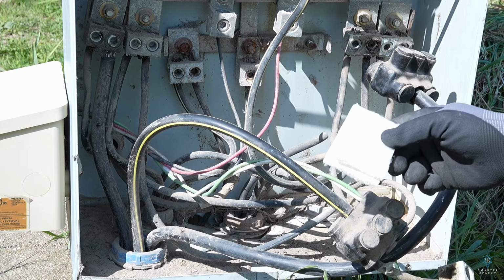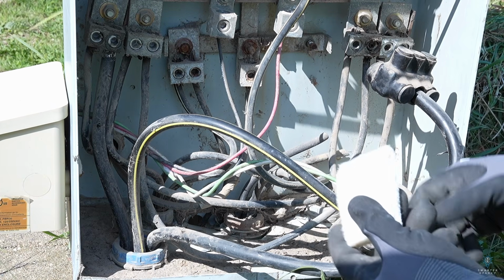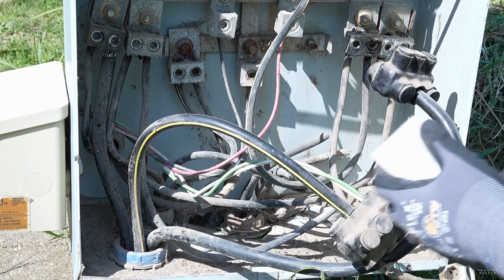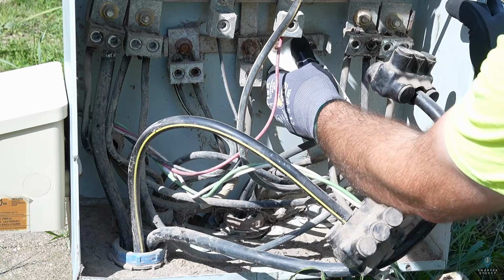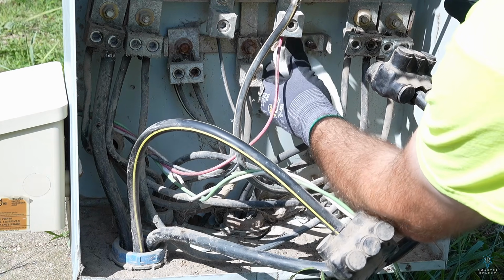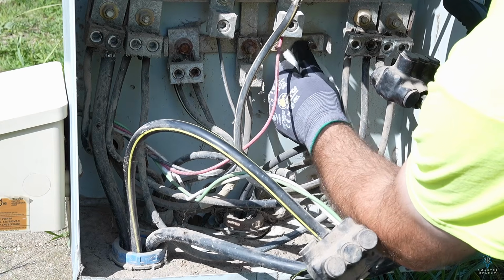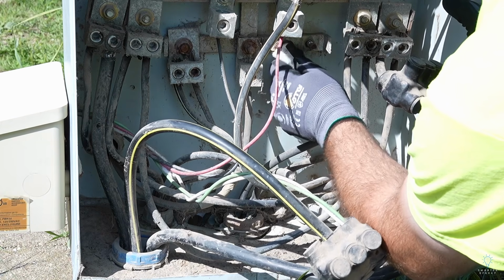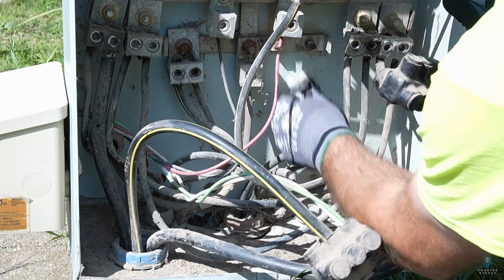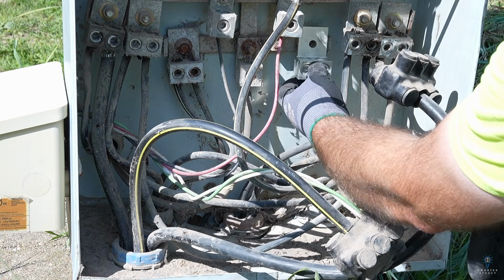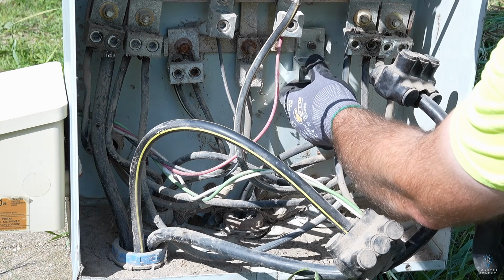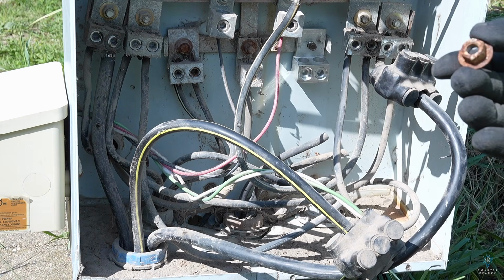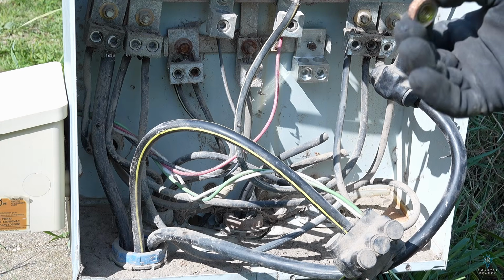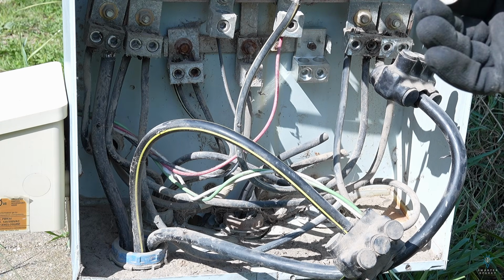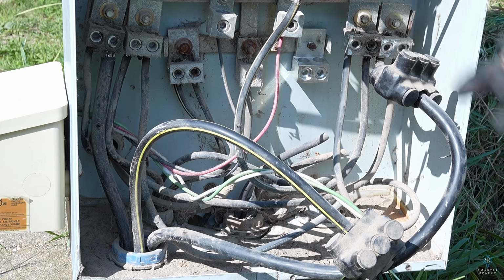So I grabbed a piece of Scotch-Brite here, white Scotch-Brite. I think this is the most gentle Scotch-Brite they have, and I am going to clean that bus bar up a little bit, but like I said, right behind it looked just fine. So we'll take our new lug and it should just slide right into place, and it certainly does. As corroded as this nut looks on the outside, it's still perfectly shiny on the inside. So I'm just gonna reuse this nut.